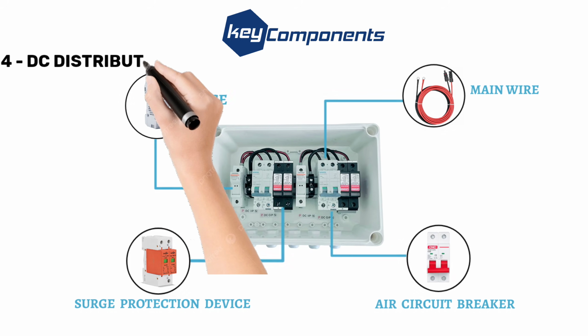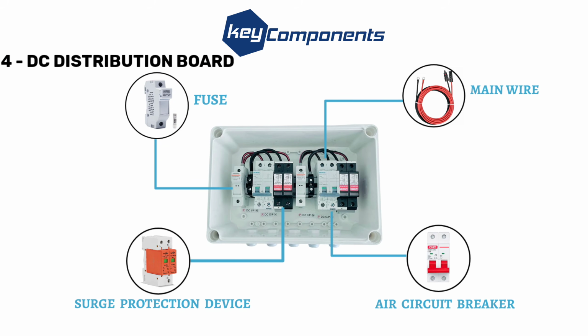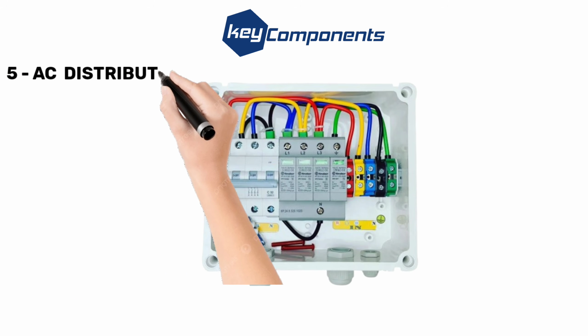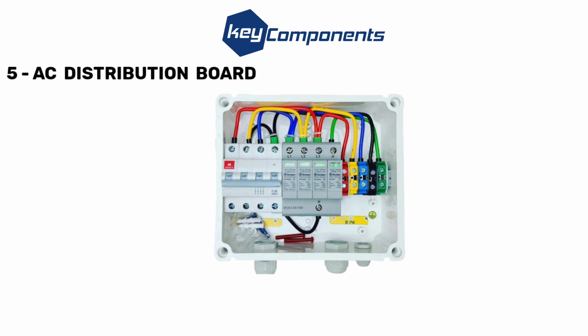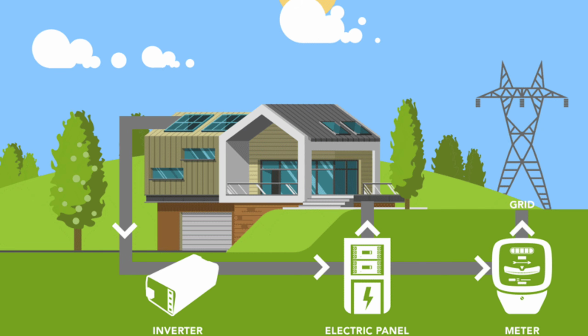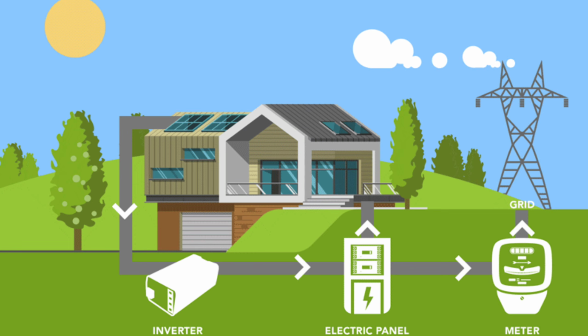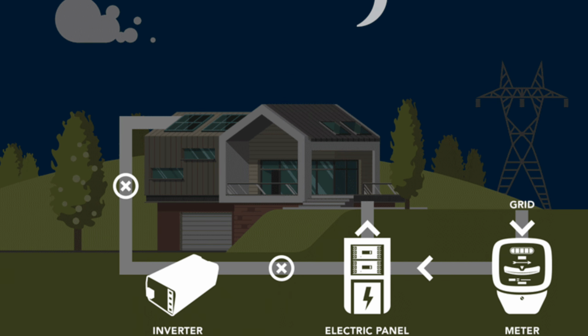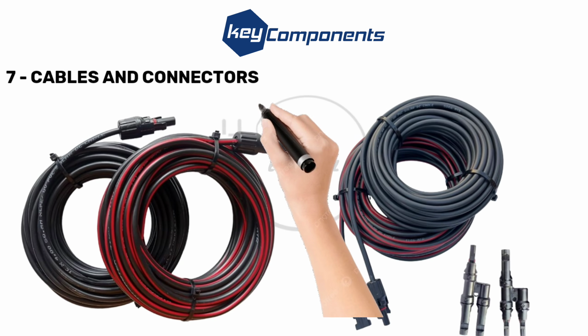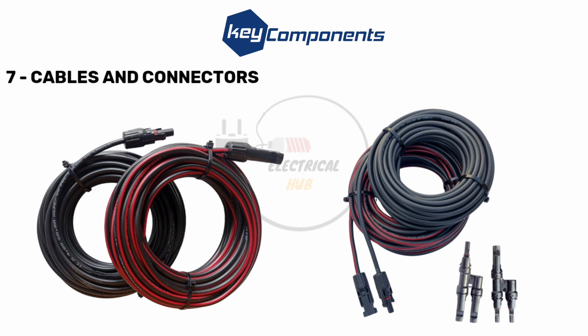4. DC distribution board, or DCDB. This houses the fuse or breakers for the DC side of the system, protecting the solar panel and inverter. 5. AC distribution board (ACDB). This protects the AC side, distributing power to your home and connecting to the grid. 6. Energy meter. This measures the electricity generated by your system and in some cases the electricity you consume from the grid. 7. Cable and connectors. Essential for connecting all the components. We will be using appropriate gauge cable for both DC and AC.